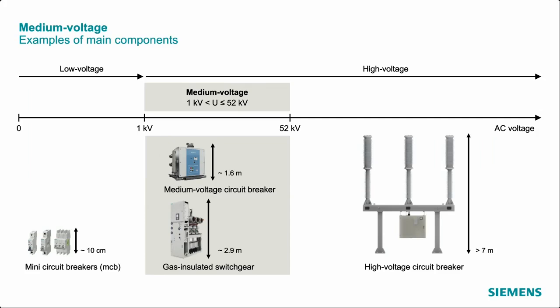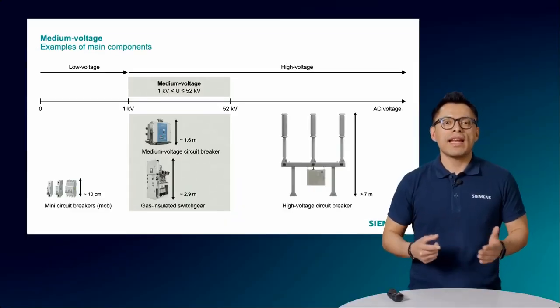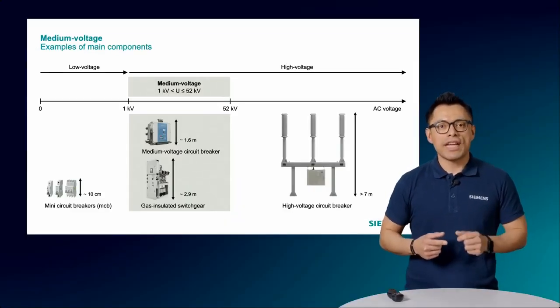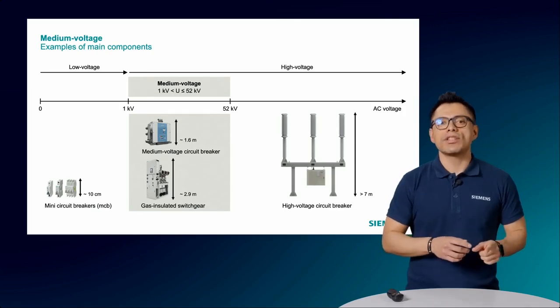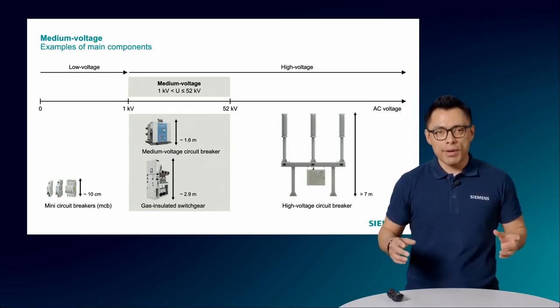Here we have some of the main components used in each voltage level as examples. Please have a look at them with special attention to the size. The size of electrical components increases at higher voltage levels. This increase is due to several factors like insulation, because higher voltages require more insulation to prevent electrical breakdown and ensure safety. This additional insulation increases the overall size of the equipment.